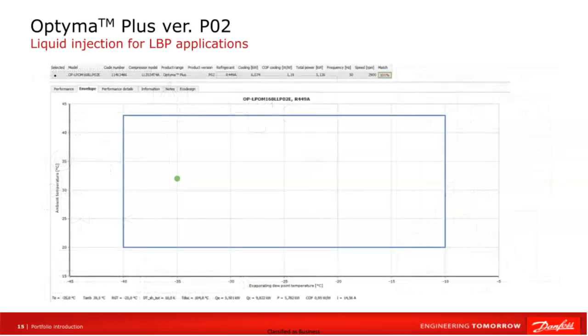Continuing the discussion of the Optyma Plus unit in the P02 version, I would now like to present the operating range of the unit for the R449A refrigerant, which is characterized by a high discharge temperature. On the slide, you can see the operating envelope of the unit, which shows the evaporation temperature range, which is from -40 to -10 degrees Celsius. This wide spectrum of evaporating temperatures makes the unit versatile and useful in a variety of applications.